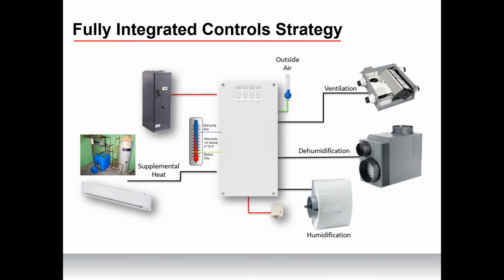This slide depicts a fully integrated control strategy utilizing Mitsubishi Electric's Kumo Cloud and Kumo Station platform as the front end for a home's HVAC system. Via this method, you can tie in your heat pump system, supplemental heat of any source, so whether that's a furnace, boiler, electric baseboard, any source, humidifier, dehumidifier, and ERV to a central panel with app-based control. Through the app, you can dictate when supplemental heat will be engaged via outdoor temperature sensors. You can control humidification and dehumidification based on relative humidity levels and manage the home's ventilation system all through your smartphone or tablet.